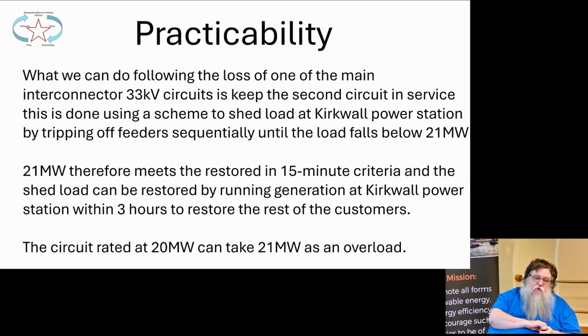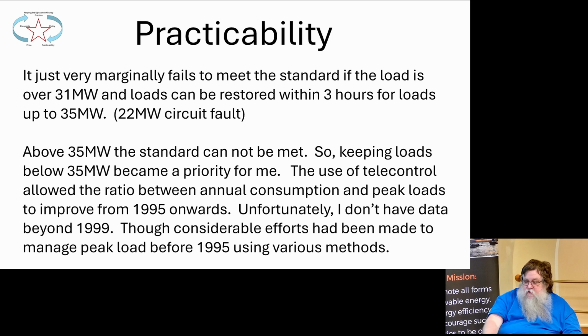The fact that we sacrifice supplies to a certain number of people, and then we've got to get guys into the power station, run it up, and once they're generating enough power, we can get all the other supplies back on. Having said that, a lot of the time, 21 megawatts is less than the actual load. So we might not finish up shedding anybody if the load's under 21 megawatts in the first place. So this scheme just marginally fails to meet the standard if the load's over 31 megawatts.